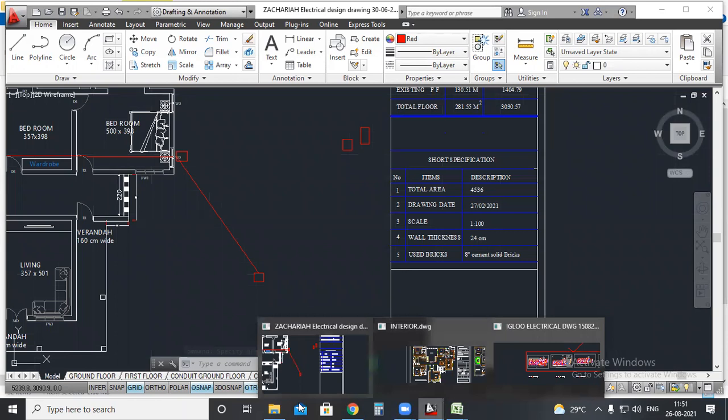So to make sure that no one can tamper the electricity, they recommend that until the energy meter you cannot take a cable underground. So to avoid that, you can provide the energy meter close to the utility pole, that means near your compound wall. From that point you can take the cable underground. So even if you tamper through the underground cable, that will come under the energy meter reading.